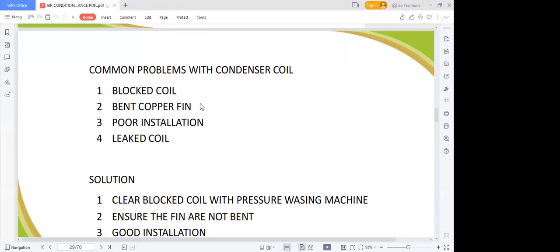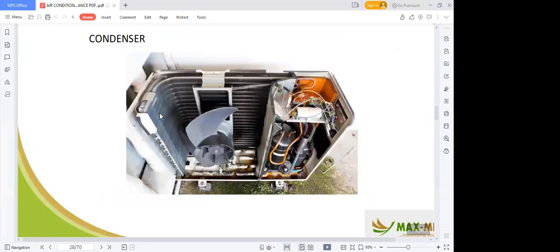Then bent copper fins. Let me go back to this. This thing that looks like silver is actually aluminum fin. If there are too many bends there, your fan won't be able to get the required air in for cooling. And if this does not get cool and the environment does not look cool, it affects your compressor. If your compressor has a protective mechanism, it shuts down. If it does not have one, it will work till it breaks down. Once it breaks down, you need to replace your compressor, and you spend about 50% of the cost of your unit just to buy a compressor for replacement. Then when you talk about replacement, don't forget the installer is going to take his money, and they are going to pay for transport. So the best bet to save your equipment is to buy a protective equipment.